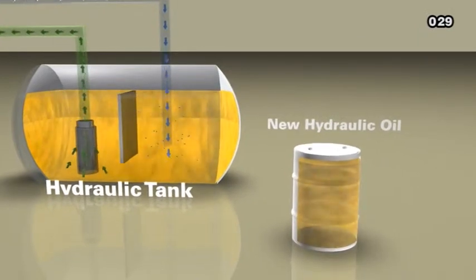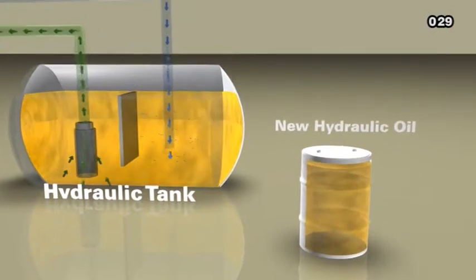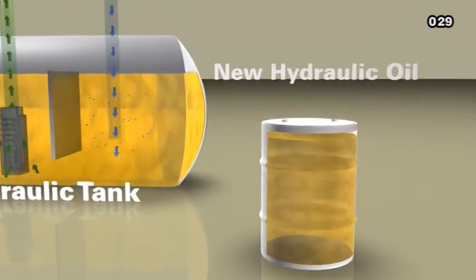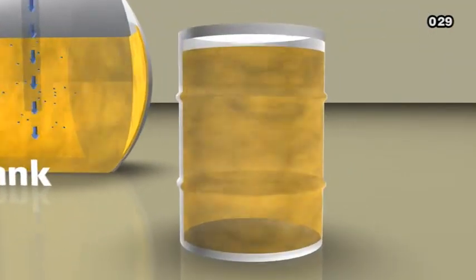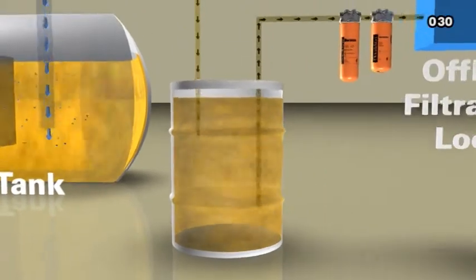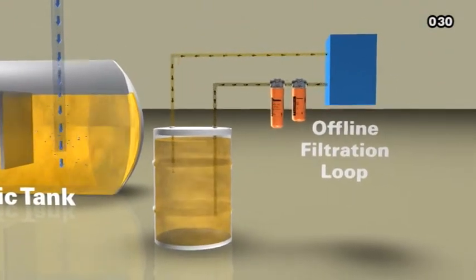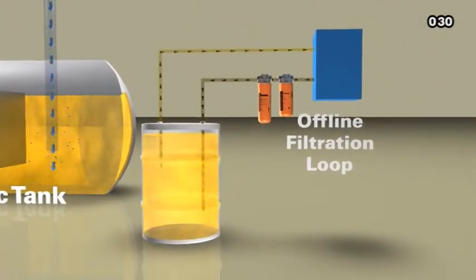At an approximate ISO cleanliness level of 21/19, it is significantly higher, that is, less clean, than OEM standards. This has prompted a leading global heavy equipment manufacturer to recommend filtering new oil before pouring it into the hydraulic tank.